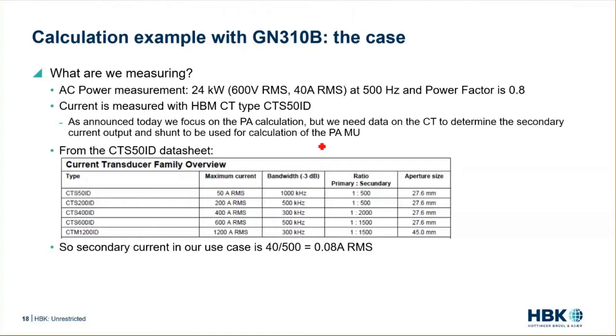The current we are measuring with a CT — an HBM CT type in a 50-amp RMS range. We focus on the power analyzer calculation only, but we need the CT data sheet to determine the secondary current output. From the data sheet snippet, we can see the ratio is 1 to 500, so if we put 40 amps into the CT, the secondary side will output 0.08 amps RMS.